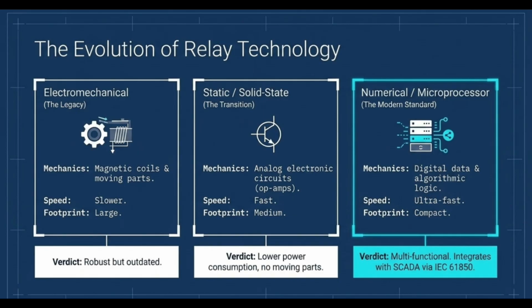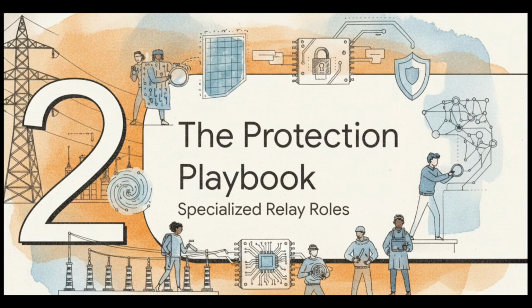And finally, that brings us to the modern standard, numerical relays, built entirely on microprocessors. Today's numerical standard is basically a high-tech Swiss Army knife. It takes raw analog signals from the grid and converts them into pure digital data. Because it's microprocessor-based, it processes complex algorithms and can perform multiple protection functions all at once. Plus, it communicates seamlessly with the grid's overarching master control system, SCADA, using the IEC 61850 communication standard. Moving right along to Section 2, the protection playbook, specialized roles for specialized threats.